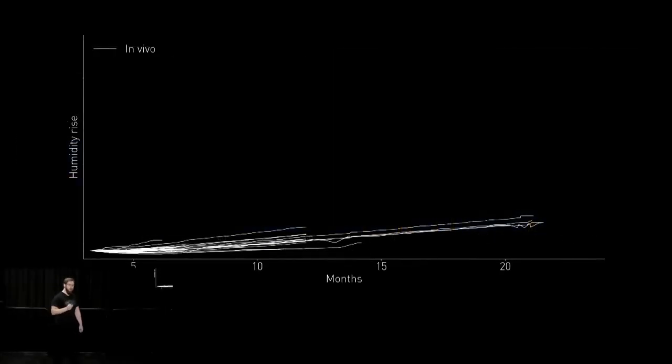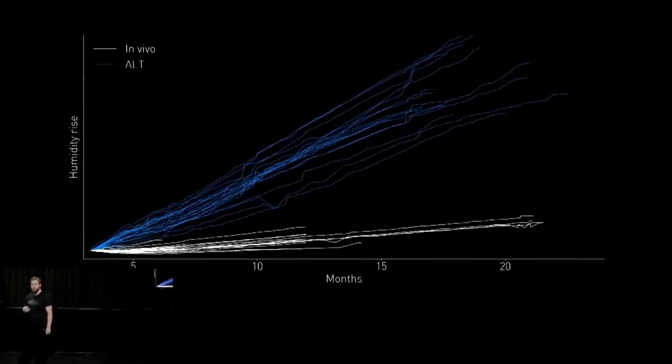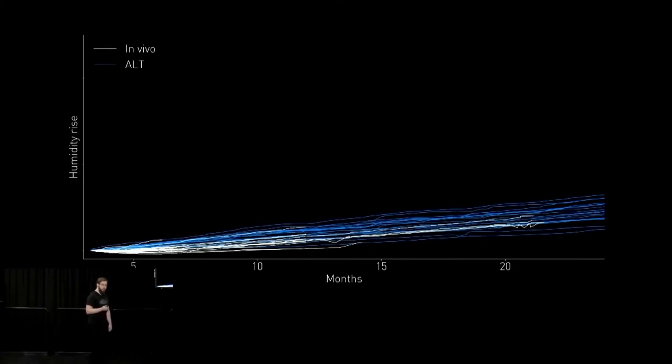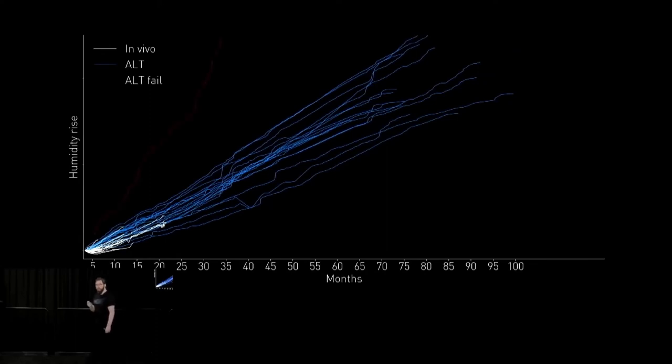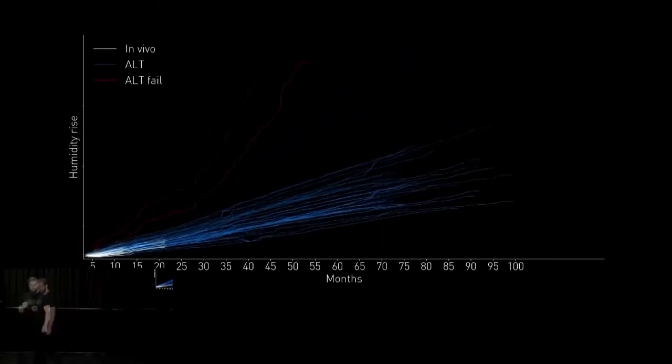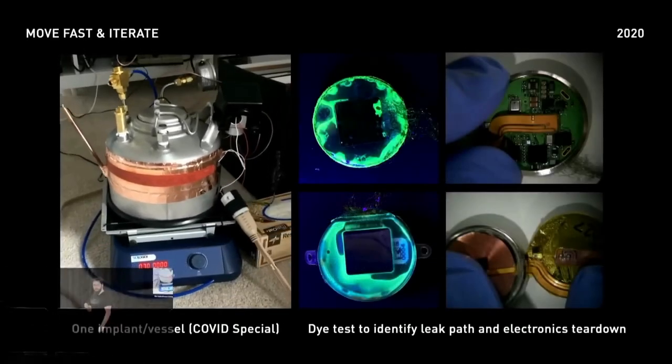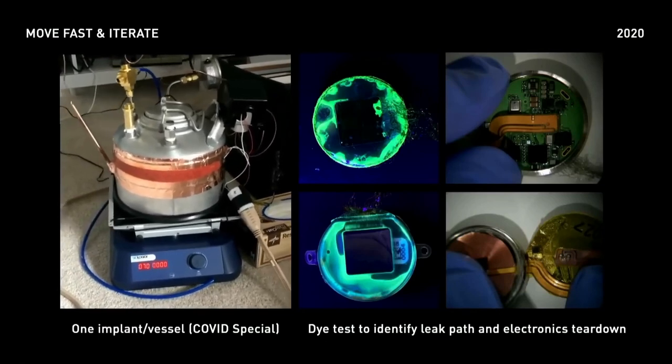As you can see, our internal humidity sensing is so sensitive, it can even detect the very small and slow humidity rise just from diffusion through our implant materials. Now, in blue, you can see that same internal humidity data, but from devices in our accelerated system. If we adjust this data for our acceleration factor, you can begin to see not only the agreement in this data, but also just how far into the future this data extends. Now in red, you can see a device which has failed in our accelerated system. This device showed an abnormal increase in humidity over the duration of many months before implant electronic failures occurred.